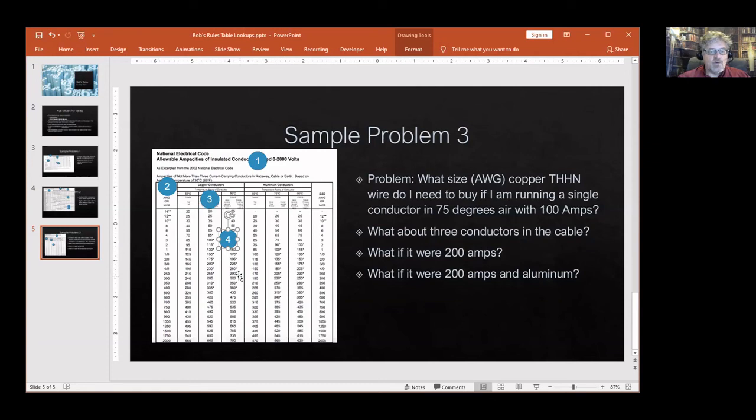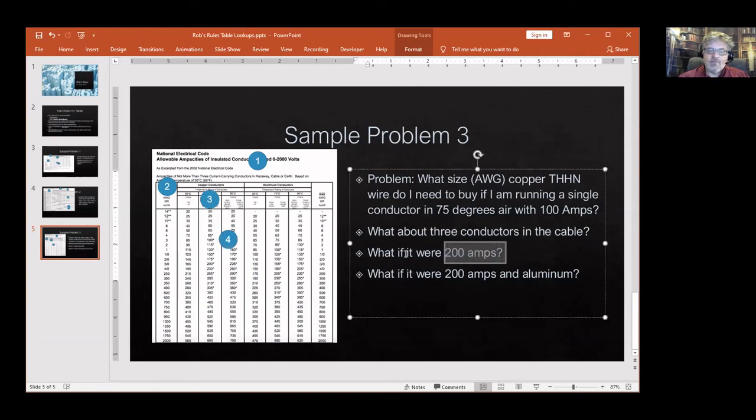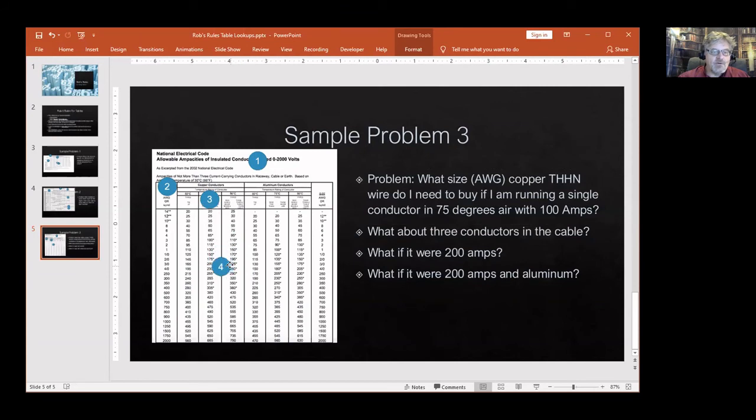Let's go on to 200 amps. What if I had 200 amps? Well then I just slide my answer down to 200 amps and I can use a three slash zero, three aught wire.